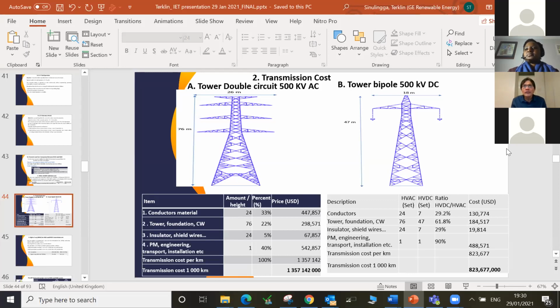So there is no direct or straight answer to compare between AC and DC. But in terms of components, for instance, for a converter station, for the valve and the converter transformer, we have a lifetime of, for instance, 25 years. Maintenance cost is very low. And the probability of damage to this equipment is so far still low, even though VSC only started operation in 1999, about 21 years until now. But most converter stations built in the first generation are still working well. And in terms of operational costs, not so high.